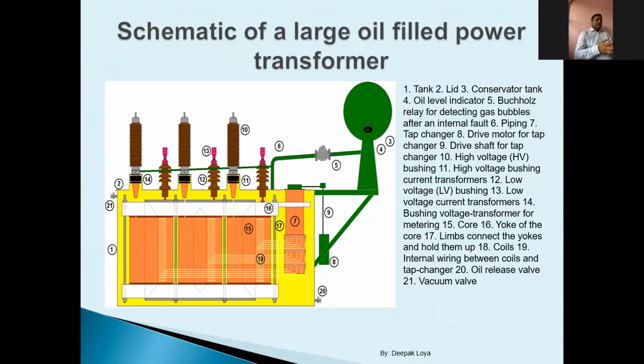Then whatever heat is produced in the transformer will affect the operation. How will it affect the operation? Because all my insulation material, paper and wood, have thermal limits. If heat is more, my paper may degrade. If heat further increases, my paper may burn. If it increases further, even wood will burn. If it increases further, even the oil may burn. So we have thermal limitations.